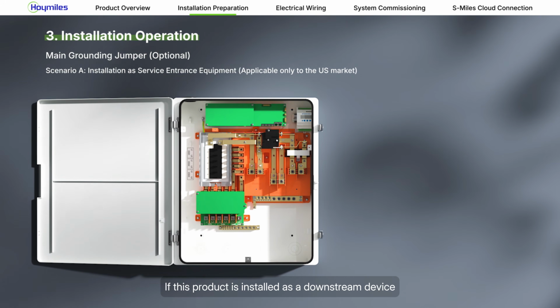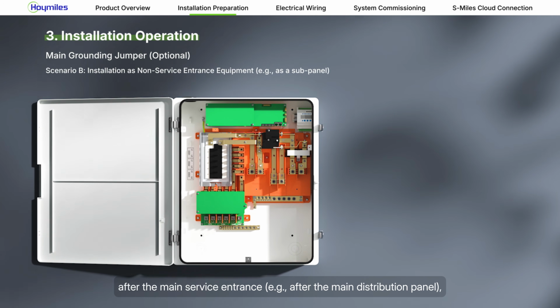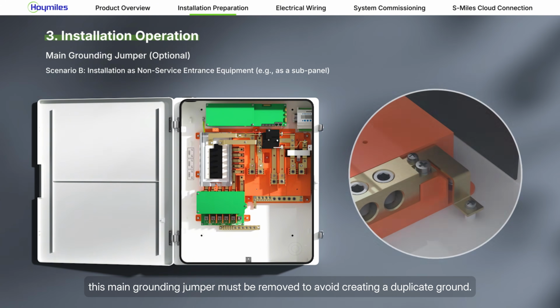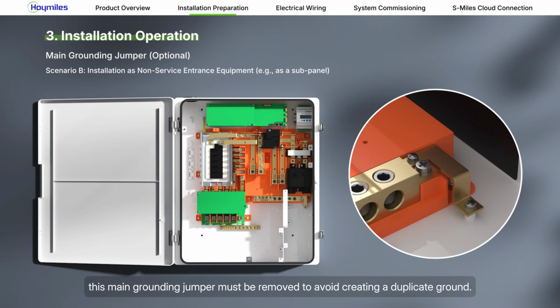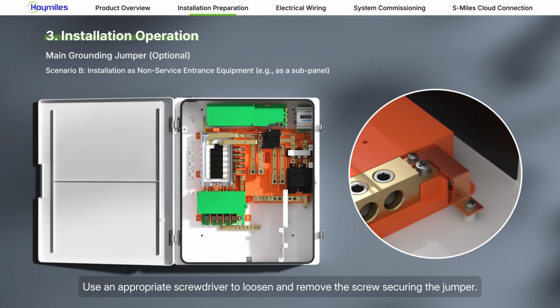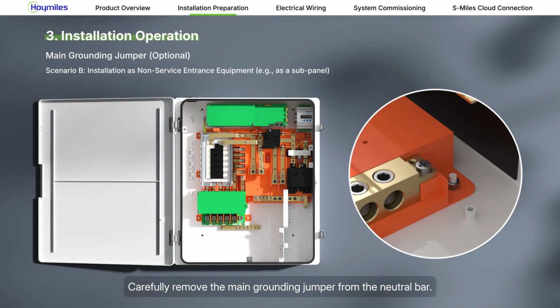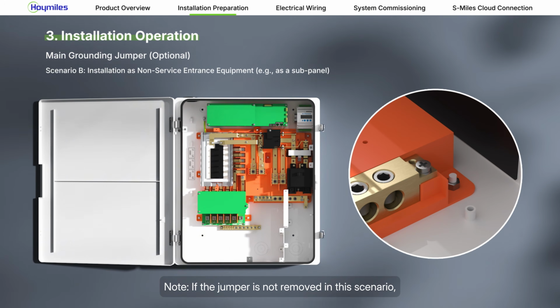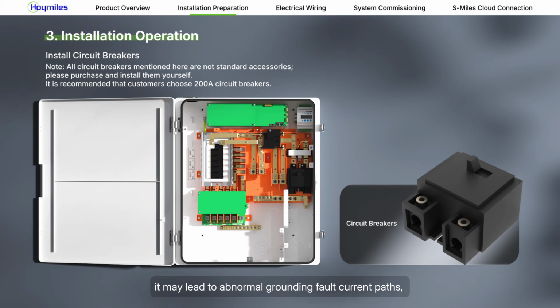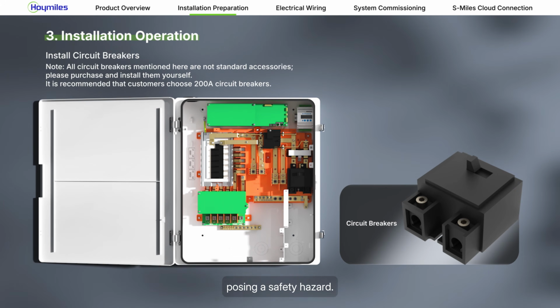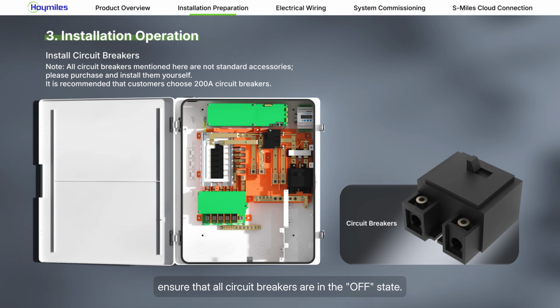If this product is installed as a downstream device after the main service entrance, this main grounding jumper must be removed to avoid creating a duplicate ground. Locate the main grounding jumper on the neutral bar. Use an appropriate screwdriver to loosen and remove the screw securing the jumper. Carefully remove the main grounding jumper from the neutral bar. Note: if the jumper is not removed in this scenario, it may lead to abnormal grounding fault current paths, posing a safety hazard. Before installing circuit breakers, ensure that all circuit breakers are in the off state.